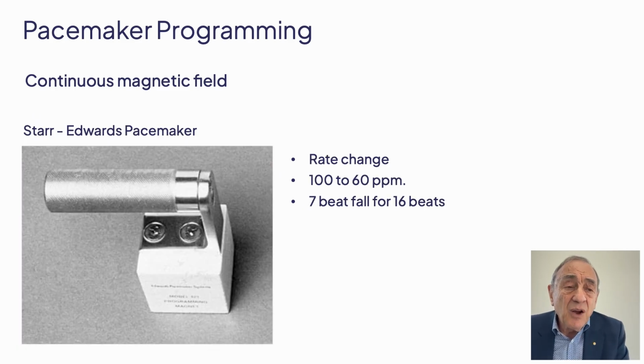Another type was a Starr-Edwards pacemaker with a very heavy magnet, placed over the pulse generator, which caused changes in rate. Every 16 beats, there was a 7-beat fall in heart rate, starting at 100 and finishing at 60. When you reached the rate you wanted, you just removed the magnet.